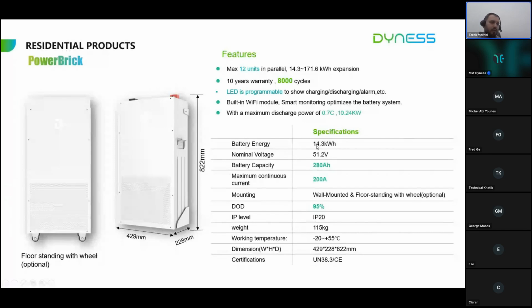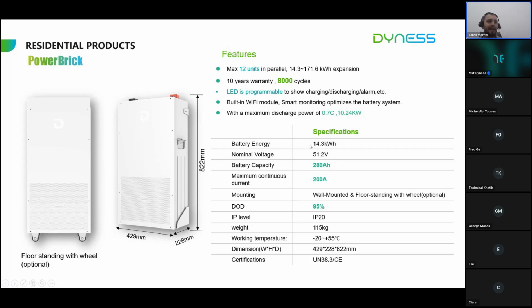Here I should add a note. Many customers ask for a 15 kilowatt-hour battery, but we should note that the new battery, not refurbished cells, comes with 280 ampere, not 300 ampere. So this results in 14.3 kilowatt-hour, not 15 kilowatt-hour. Many advantages of this battery: its compatible size. It can be used for 12 units in parallel, which means an expansion of about 171 kilowatt hour.